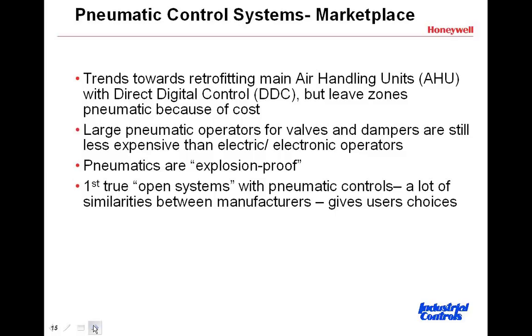From a repair and service standpoint, those pneumatic operators have been around for so long, and to repair one normally is just a rubber bladder — a diaphragm. The Johnsons and Honeywells: those parts are still available even though the actuators themselves have long been obsolete — the springs are available, diaphragms are available. It's imperative to have the right model number, and of course you must do it safely, because when you pull the top off there's a big spring waiting for you. That has to be done according to manufacturer's instructions, but they are very maintainable.